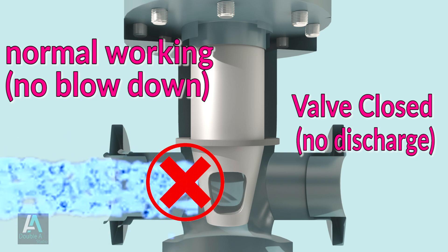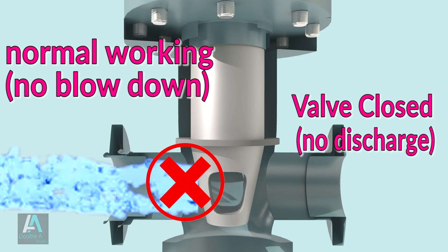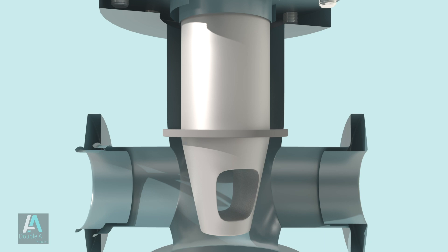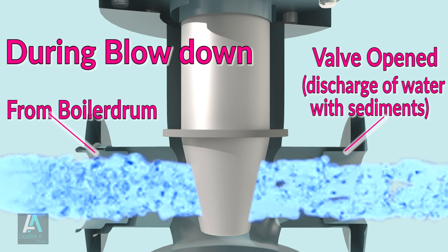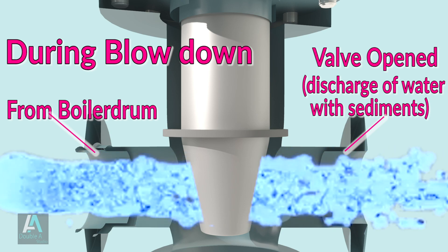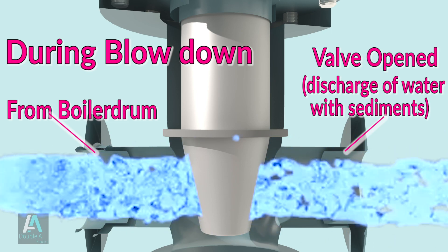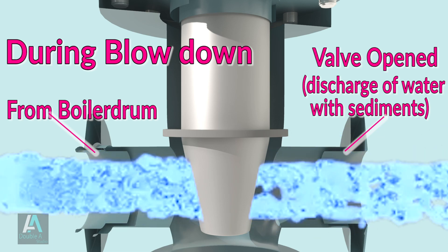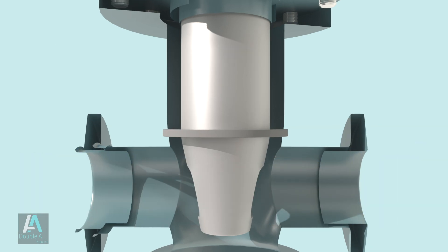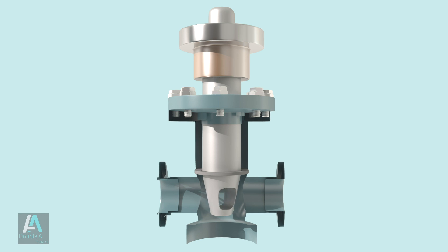In the closed position there is no discharge of water from the boiler. When blowout of sediments is desired under working condition, the plug of the blow-off cock is turned so that the hole in the plug comes in line with the outlet pipe. Water from the boiler rushes out from the bottom of the drum, removing sediments, scale and other deposits. After the required blowout, discharge is stopped by turning the plug back to its previous position.